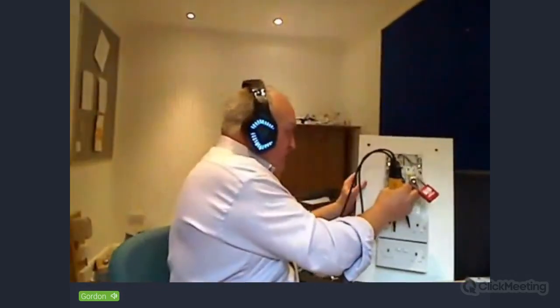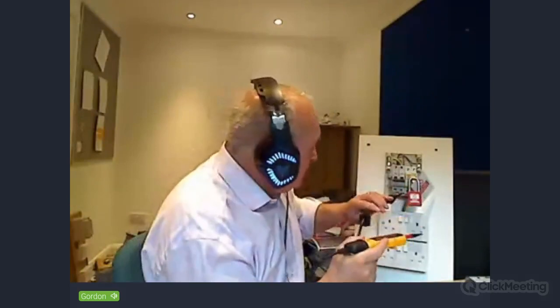What do we do then? We test between terminals - I'll put that back over there. It doesn't matter what sequence you do this in, but what I like to do, if you think about it, is: if I put that onto the mains and the live terminal was live, that end would be live as well, which is quite dangerous. Even though I know it's padlocked off, safety first, in my opinion.